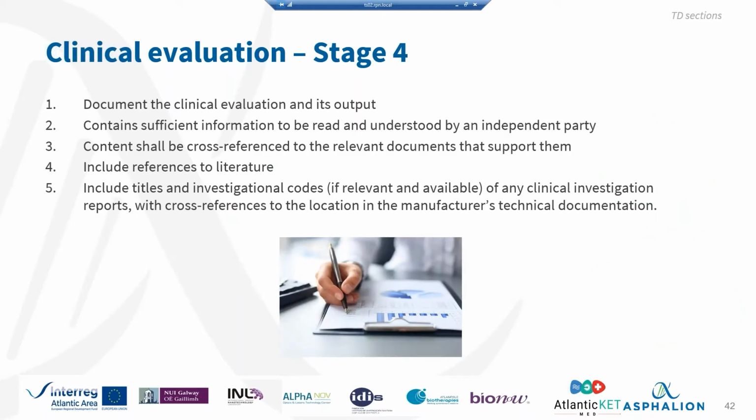Okay. Once you have analyzed all this information, you will write down this clinical evaluation report. This clinical evaluation report will summarize all the process. You will go from scoping to identification of data. Where are you retrieving the data from? All these details have to be detailed inside the clinical evaluation report. You can find guidance on how to do this in the MedDev 2.7, as it indicates every part of the clinical evaluation report and the typical expected sections of your clinical evaluation report.